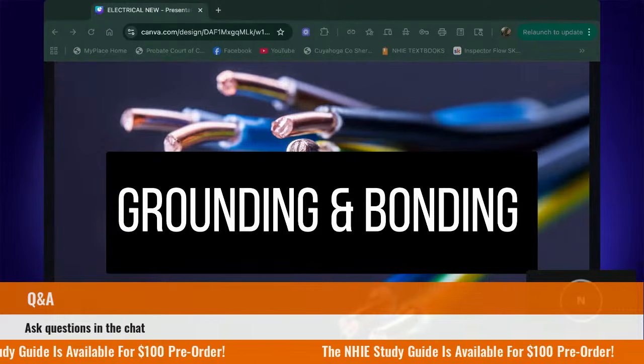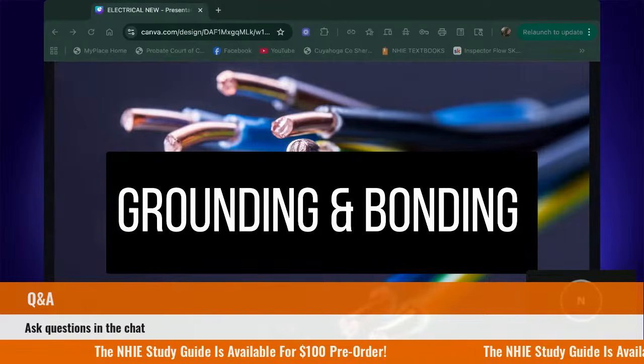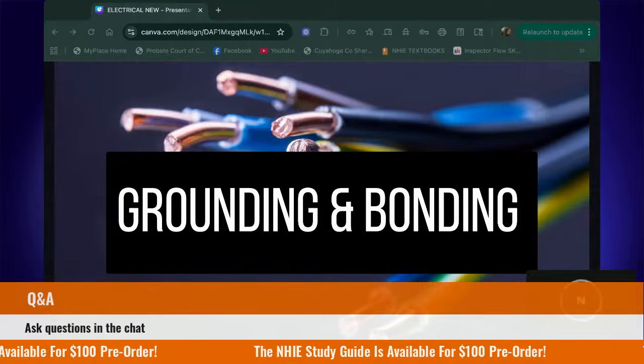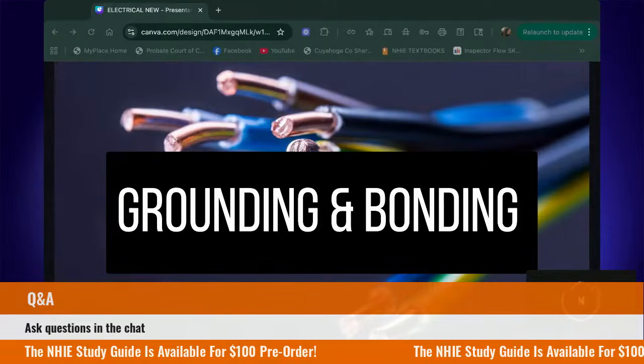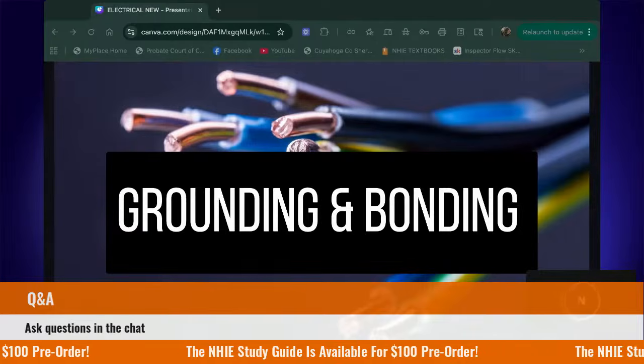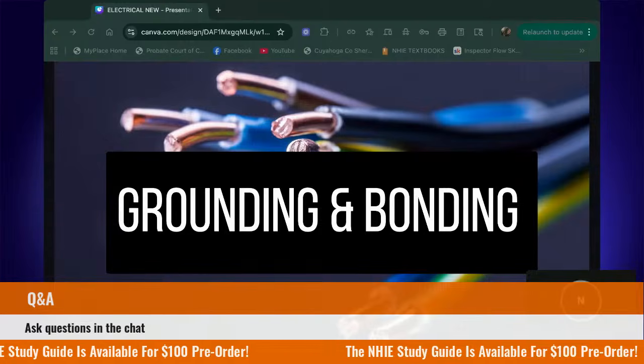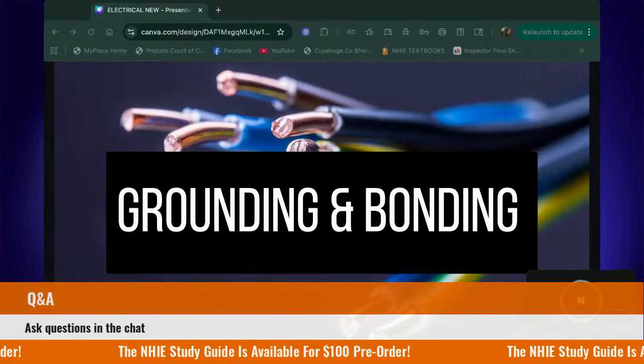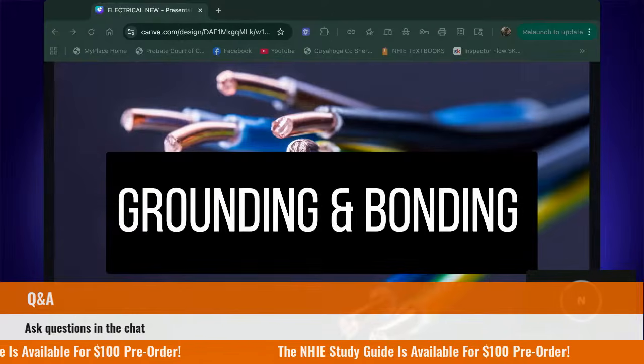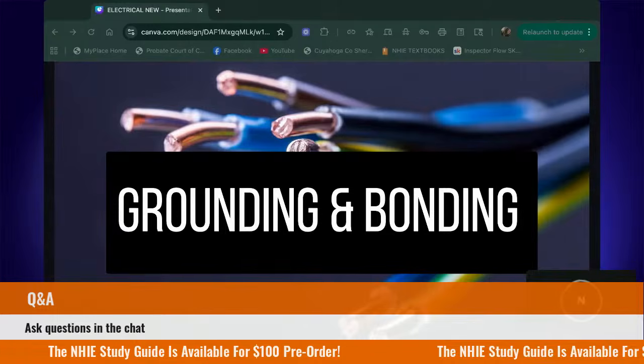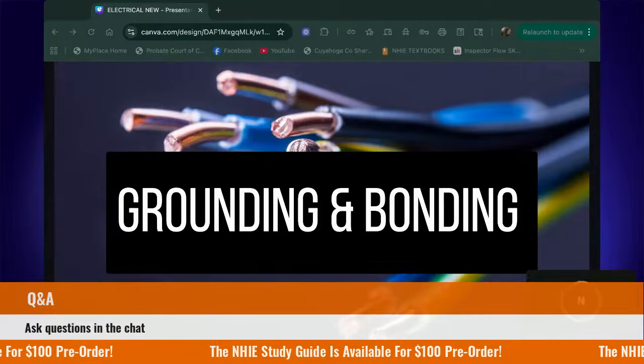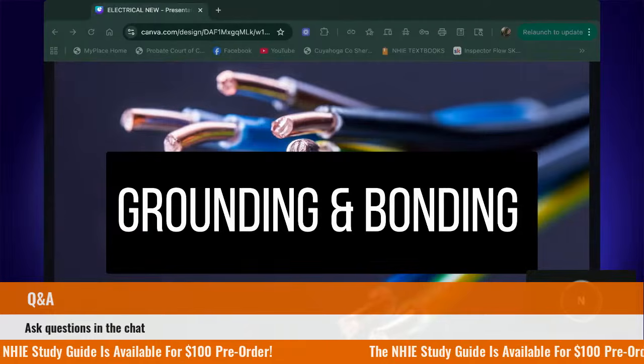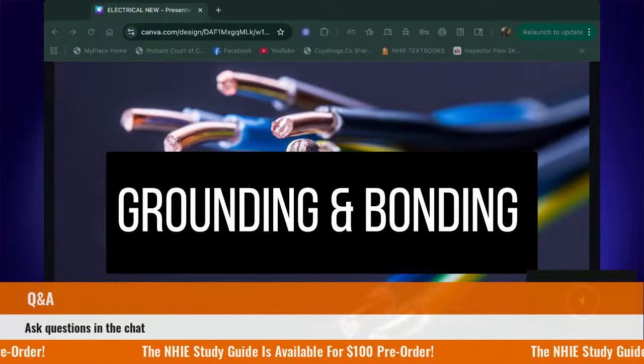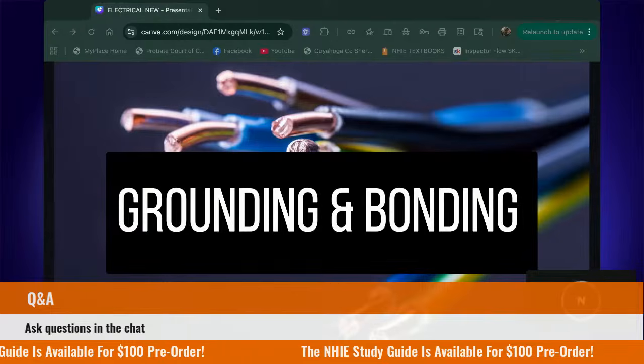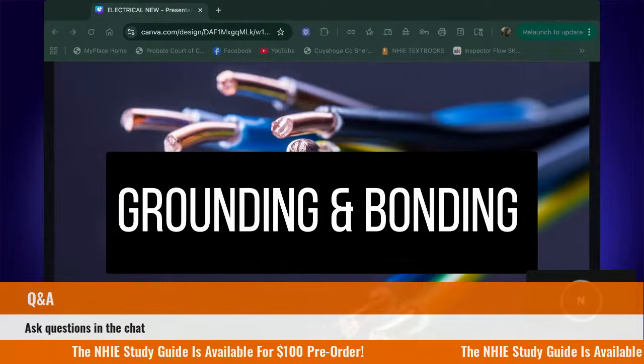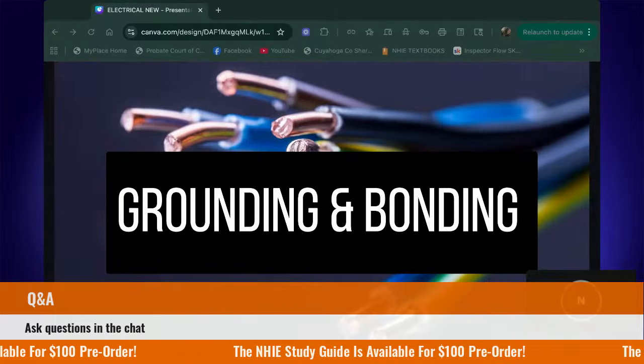Do you remember when we were learning about plumbing and we were talking about bonding the plumbing lines and why that needed to be? Well, that's because the plumbing lines were made of copper. Copper is a very conductive material. You will find here that when we start to talk about the wiring, most of our branch circuit wiring is copper because it does a good job at carrying electricity. It doesn't know that this particular copper tube is supposed to be carrying water and this one is supposed to be carrying electricity. So that's why we have to bond those plumbing lines into the bonding system, so that if we were to happen again to have a fault, we don't want to have current traveling on our copper plumbing lines. Okay? So it is creating this path. We're connecting everything so that it can travel on that path to ground in the event of an issue.